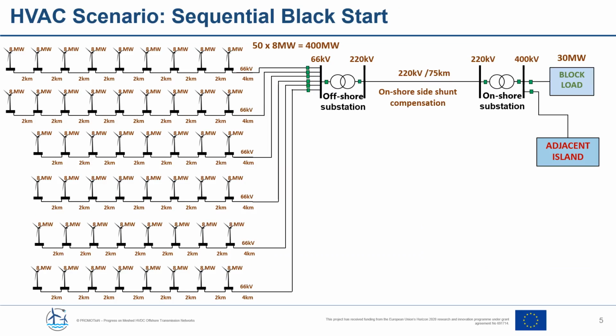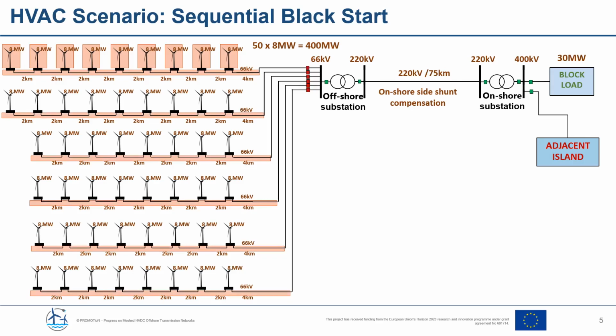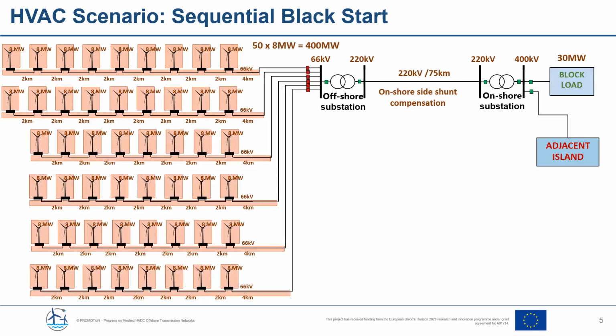The scenario we've considered for black start operation is a 400 megawatt wind farm consisting of 50 wind turbines of 8 megawatts each and located 75 kilometers away from the onshore HVAC substation. The connection process starts by a single wind turbine energizing the first string cable, then the rest of the wind turbines of that string. Then we will have enough reactive power to energize the whole array, followed by the rest of the wind turbines. At this stage, the whole system will be operating in an island.